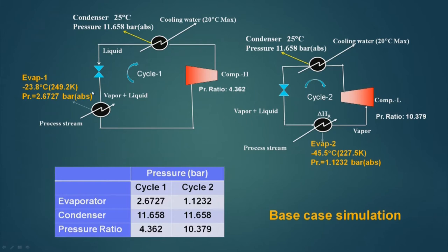Similarly for cycle 1, the evaporator operates at minus 23.8°C and 2.6727 bar. The vapor must be compressed to 11.658 bar to reject heat to cooling water at 20°C maximum, giving a pressure ratio of 4.362. Comparing the two cycles: cycle 1 evaporator is at 2.6727 bar, cycle 2 is at 1.1232 bar, and both condenser pressures are 11.658 bar. Cycle 1 has a pressure ratio of 4.362 and cycle 2 has 10.379. This is the base case simulation.